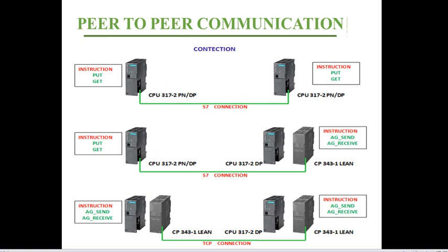Let's look at the layout. For the first type — peer-to-peer communication — the two PLCs are connected by Profinet. The two PLCs must have different IP addresses within the same network, and the connection type is S7 connection.